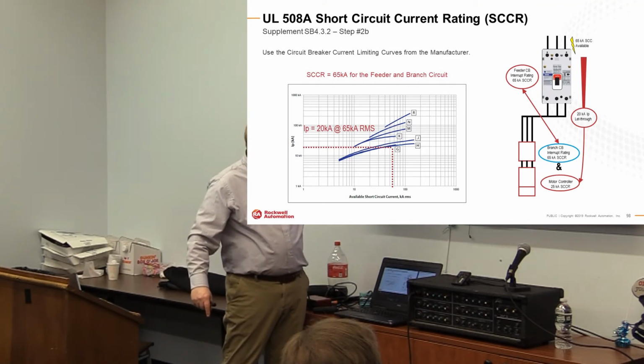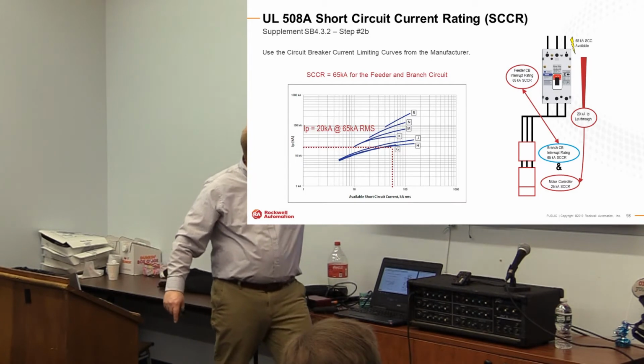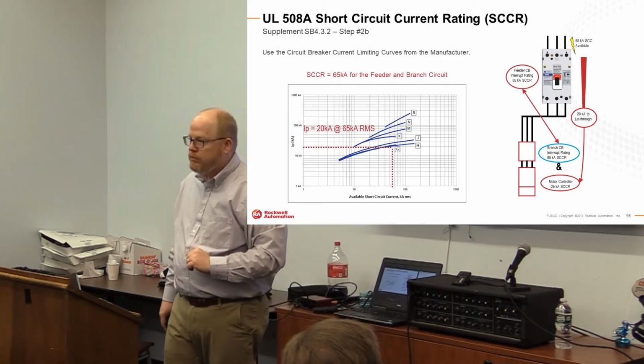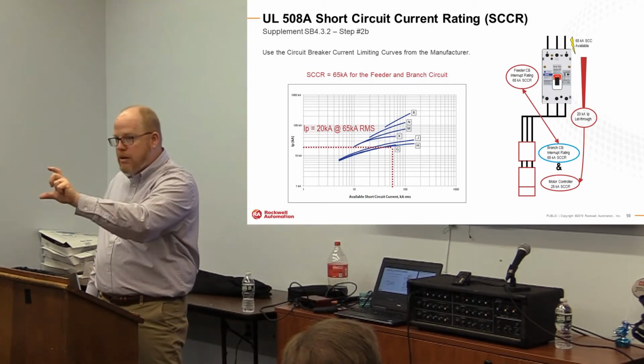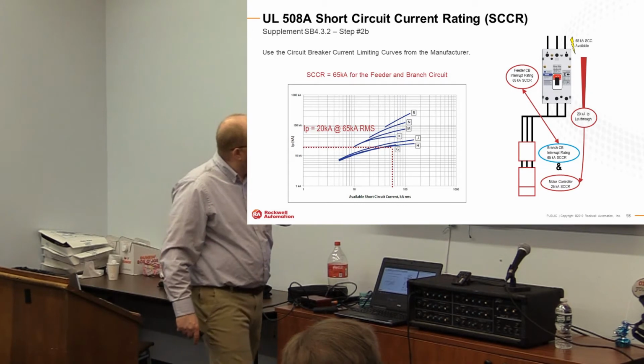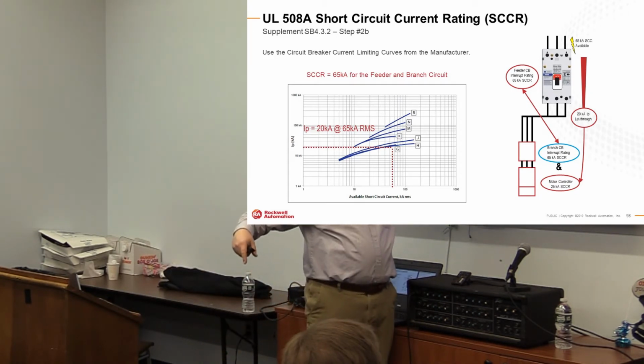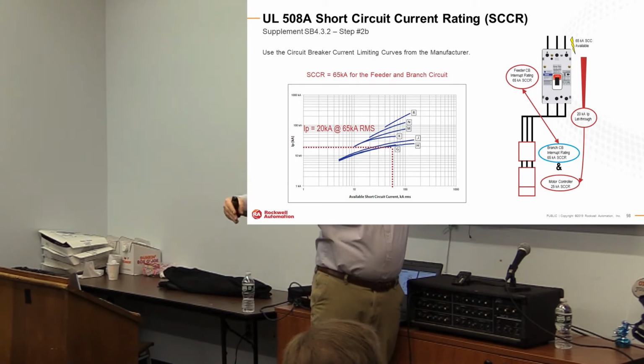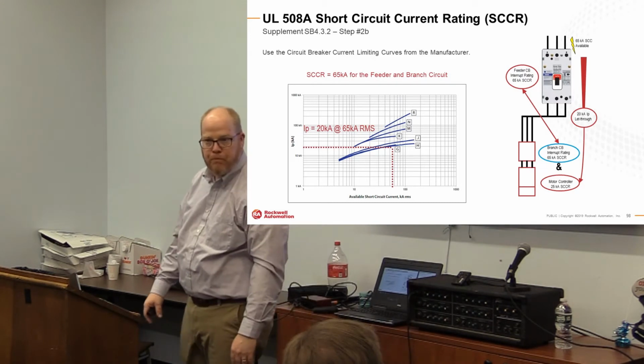So you make that evaluation by reading the trip curve. You then have to make sure that everything downstream is better than 20,000, either as a combination rating or as a component. If that's the case, that's your first hurdle. Then you go up to each branch and ask, is its interrupt rating as good or better than the feeder? Those are the two ands, hurdle number 2, then you are able to claim it.